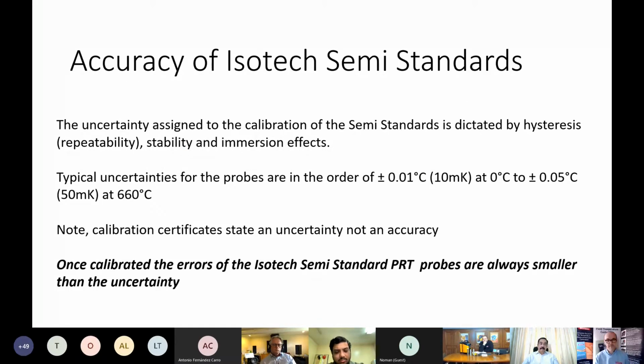So what's the accuracy? Well, the uncertainty assigned to the calibration of the semi-standard is dictated by the hysteresis, the repeatability, the stability of the probe, and the immersion effects. But the typical uncertainties for probes are on the order of 0.01 to 0.05, 10 mK at 0 degrees C, 50 mK at 660. Now note our calibration certificates are ISO 17025, so they are specifying uncertainty rather than an accuracy. But once we've calibrated our systems, the error of the semi-standard PRT will always be smaller than the uncertainty. So we can see it as the same. The uncertainty we quote is the uncertainty, but any offset or errors or accuracy will be within that uncertainty.